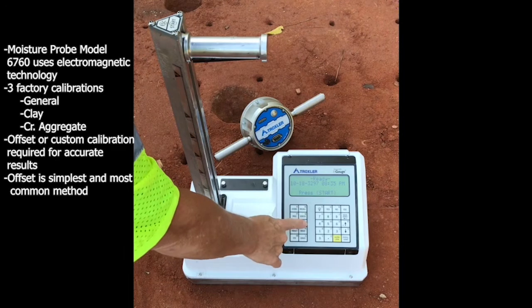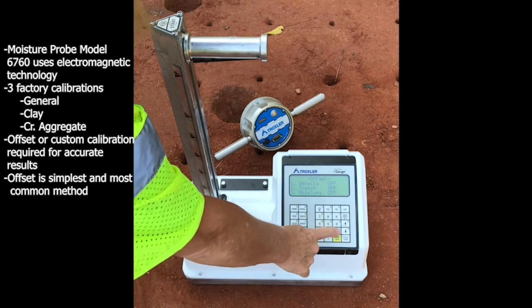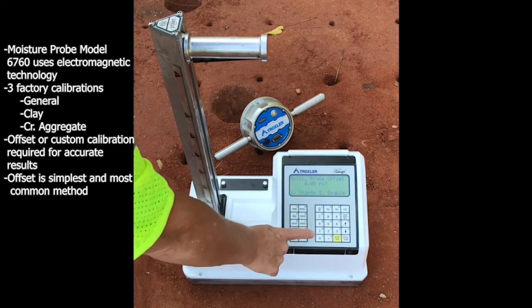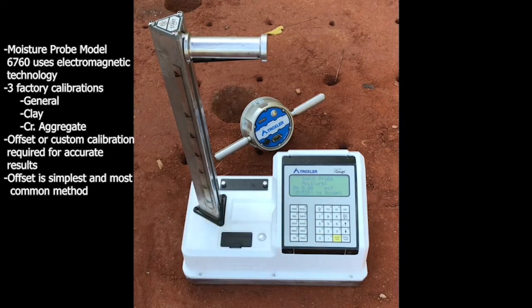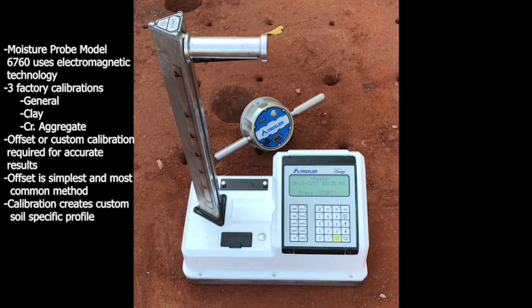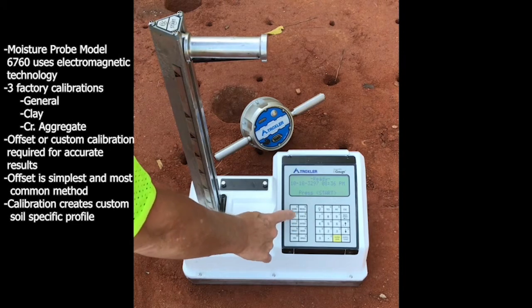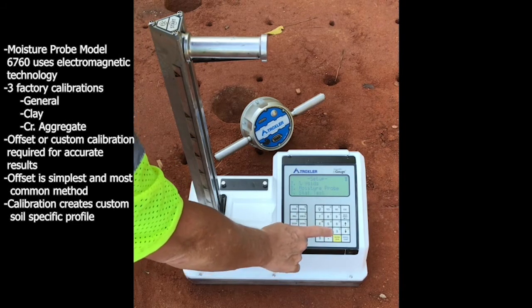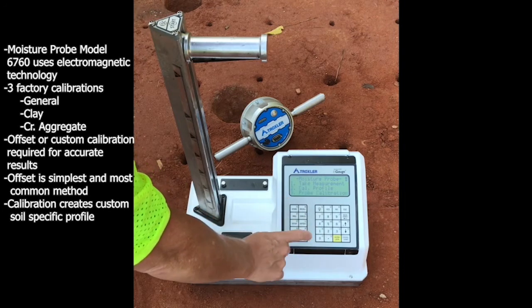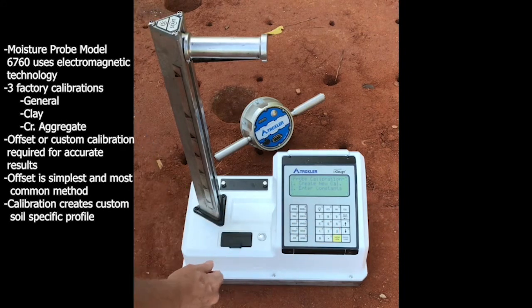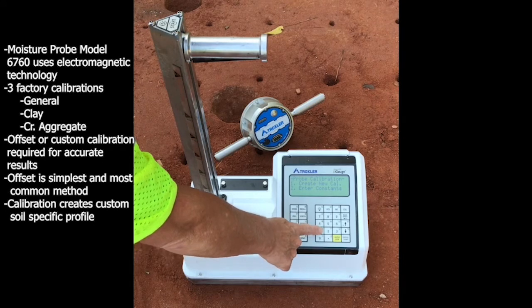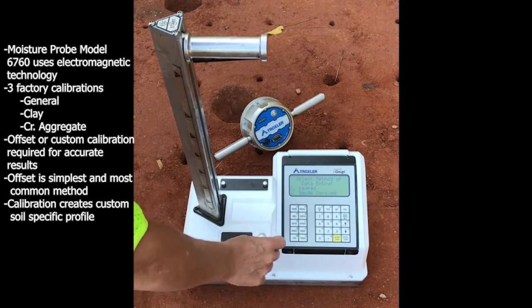This is available under the offset option, and it's number 3, moisture. And to create a new one, you would select 1, change. We'll discuss the procedure in this demonstration. A moisture probe calibration is another option. This procedure creates a new moisture calibration profile, which is then stored for later use. This is in the same menu we looked at earlier: Setup, 8, Moisture Probe, and 3 would be Probe Calibration, and 1 would be Create a New Calibration. And we'll discuss that procedure.